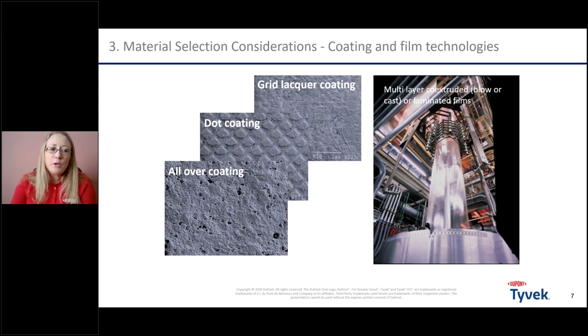In terms of Tyvek, you have principally three different coating solutions, like a water-based or EVA-based all-over coating, or you have hot melt dot coating or grid lacquer coating, depending on the application and the materials you want to seal with, etc. Also, there are some differences in porosity, but all allow sterilization gas through.